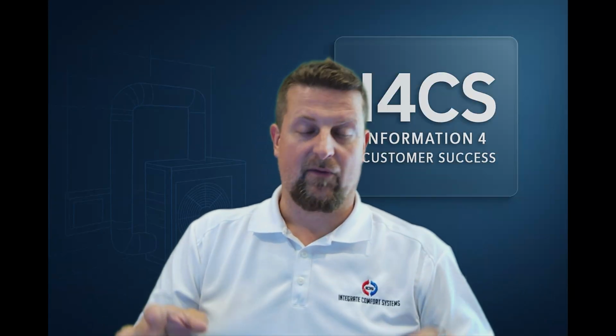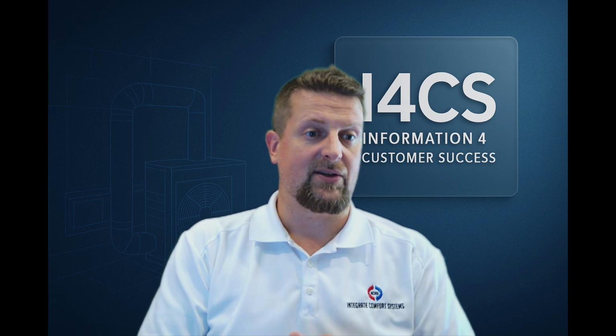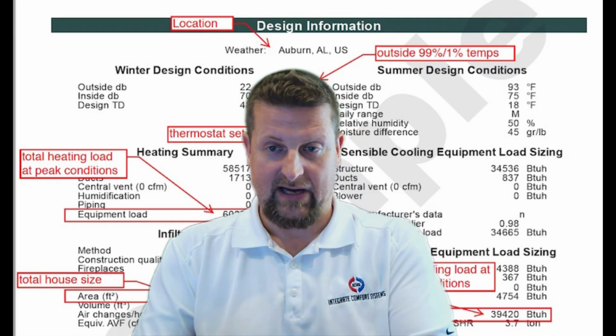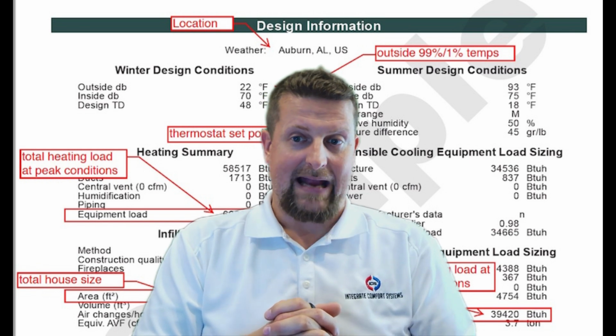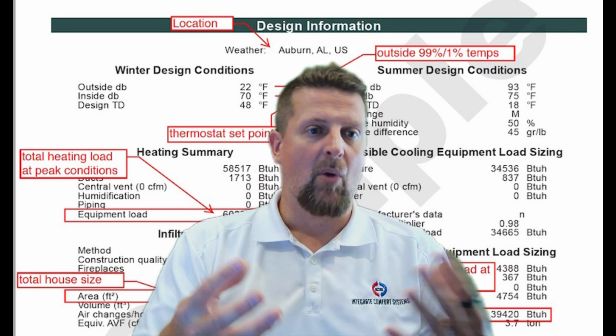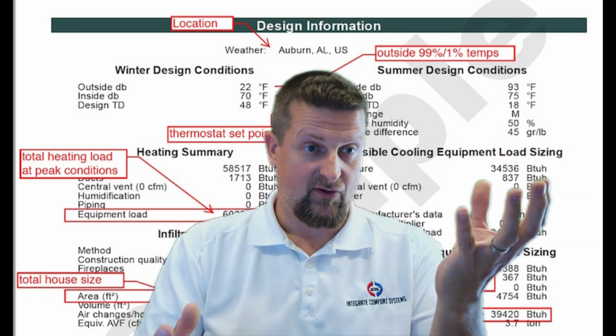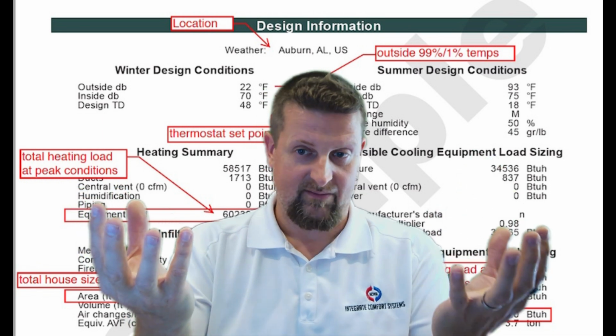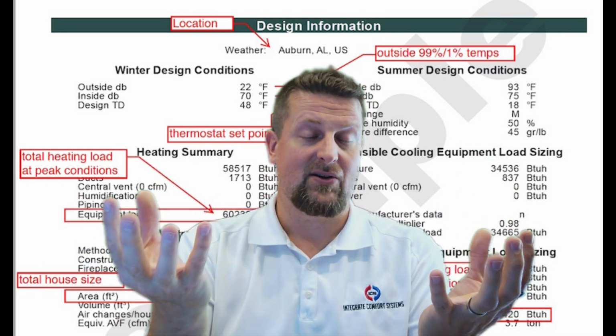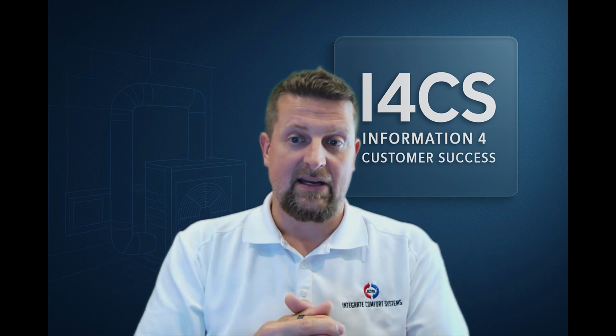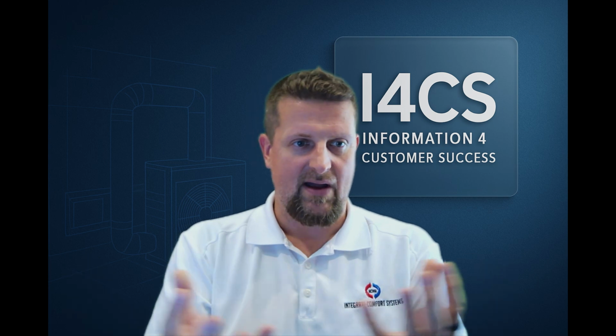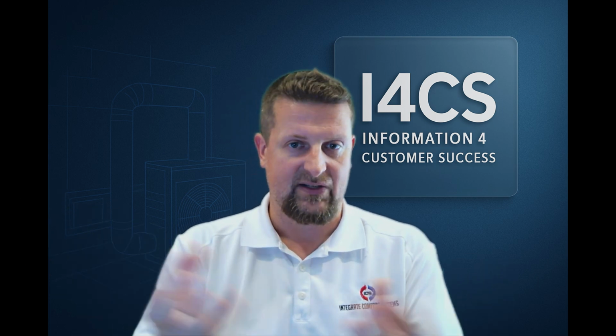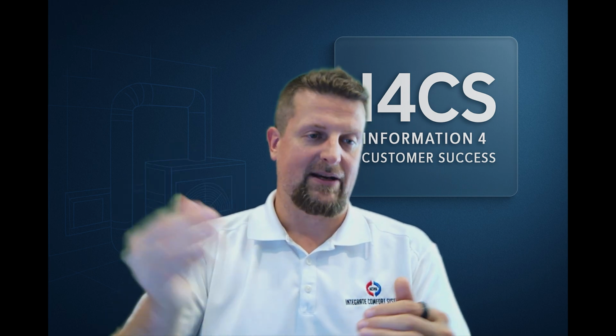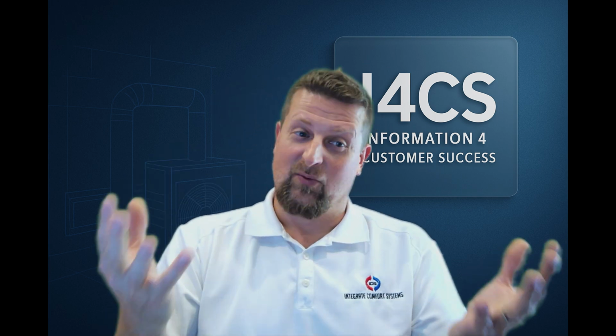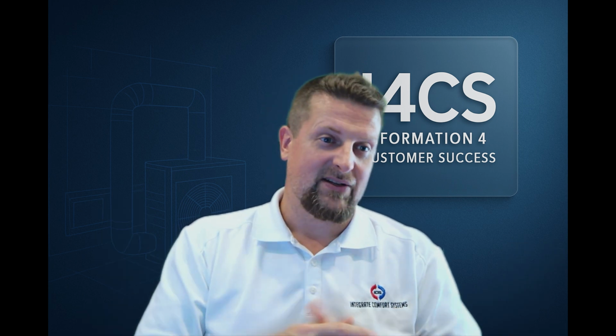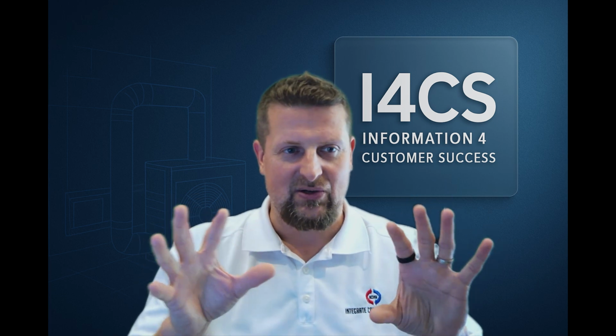Now, another reason your house may perform a little bit better besides the insulation is also that when we do these load calculations, we don't always end up with equipment that's perfectly sized for the load calculation. The perfect example of that might be a calculation that came out with 25,000 BTUs. Well, most equipment will fall either into the 24,000 or so BTU category, and the next step up is the 30,000. So your house may have needed a 25,000 BTU unit, but you ended up with 30,000 BTUs. So you got a little bit more than really the load calculation called for. So it all depends on where exactly you end up. Sometimes you have a slightly oversized system just because that is the proper size system anyway. So you never land perfectly on your load calculation a lot of times, but sometimes you may. Sometimes you may have a 23,000 BTU cooling load that you need, and the proper size equipment is the 24,000 BTU piece of equipment. So you only really got that 1,000 BTU extra.